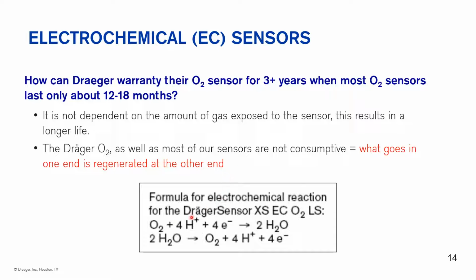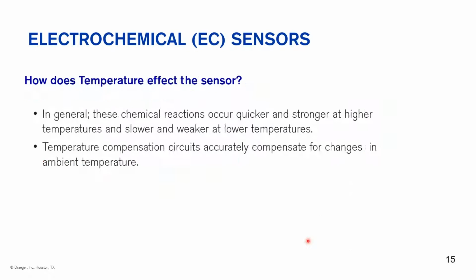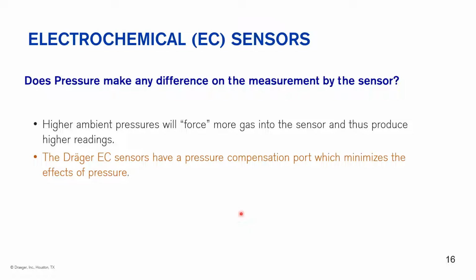Basically, we call our O2 sensors an O2 pump. So kind of what goes in one side, there's a reaction. I'm not a chemist, but O2 goes in, it reacts, it creates the 2H2O. And then on the counter electrode, the 2H2O reacts to basically put everything back the way it was. Temperature: hotter temperatures can increase the speed of reaction, whereas lower temperatures can slow it down. Instruments do have temperature compensation within them to compensate for those changes in temperatures. Pressures: if you get a change in pressures, you can have an effect on the sensors. Generally, I'm going to say more towards the oxygen sensors. Again, ours have a pressure compensation system in it.